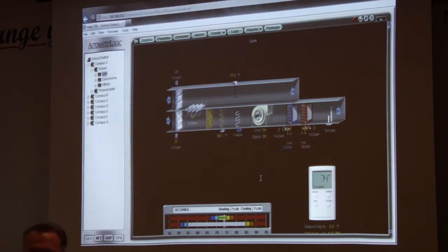Real quick, this is just a quick check to see where we're at. Would you lock off a supply fan if you wanted to go work on the fan? You would lock it off using our software to go into the fan, right? You cannot trust that output. Anything could short that. All we do on our output side, if you look at it really close, is whatever's on the first screw, each output has 2 screws.